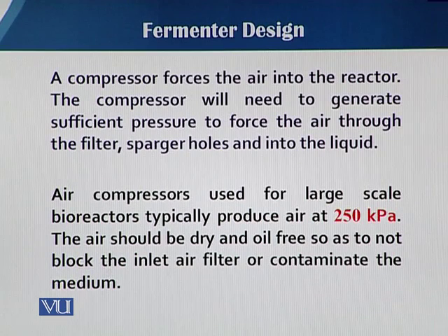That's why air compressors used for large scale bioreactors typically produce air at 250 kilopascal. The air should be dry and oil free. Why? Because when compressors move, their pistons have lubrication, so when they compress the air, oil particles can come into the fermenter vessel along with the air. Sometimes it also mixes with water vapors.